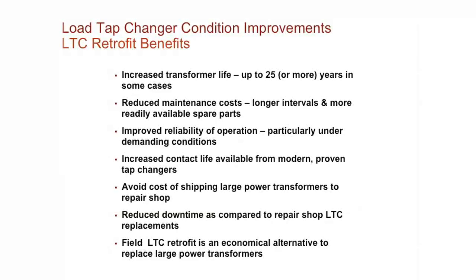So some tap changers we can get in about three months, some are about 6 months. So it depends on the tap changer, depends on the type of retrofit that we're going to be doing. You do get the improved reliability, basically because of the tap changer being brand new. Our new VR LTC will talk about the number of operations, how long the maintenance cycles are, but they're about 10 times longer than some of these older models that you have out there.